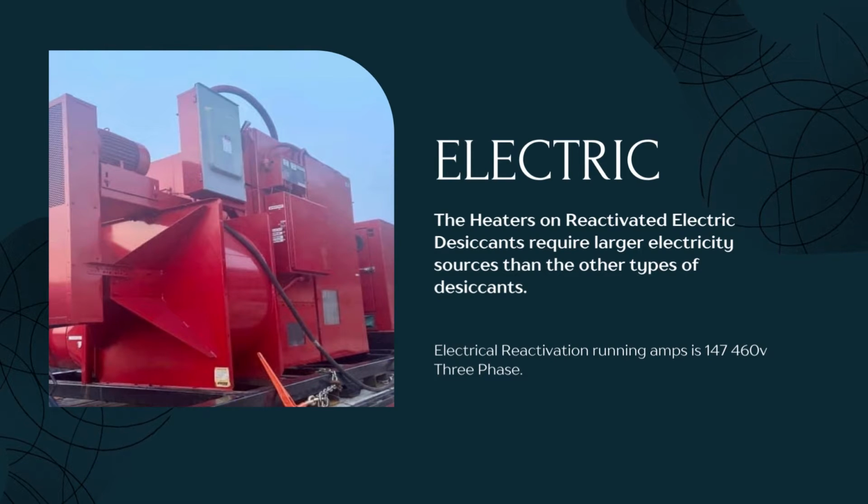This is a 9,000 CFM all electric unit. The heaters in it run on all electricity. It takes a very large generator to run it, usually somewhere close to 200 kW, and she will suck some fuel, about 8 to 9 gallons an hour. They do have their advantages. If you have problems getting diesel, you've still got to have it for the generator, but sometimes they come in handy for the all electric part of it. And it's a Cargocaire unit, very good machine.